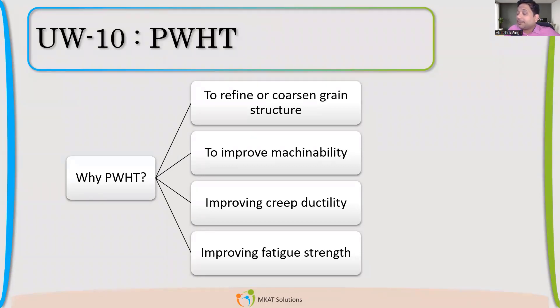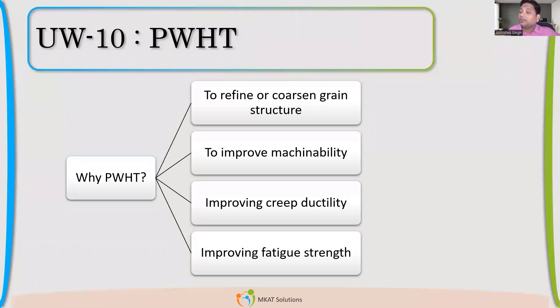We saw in the earlier chapter, whenever we have lethal service which is very critical — when we have boilers where pressure is more than 50 PSI, or direct firing in the pressure vessel — all three cases, the post-weld treatment requirement was mentioned.